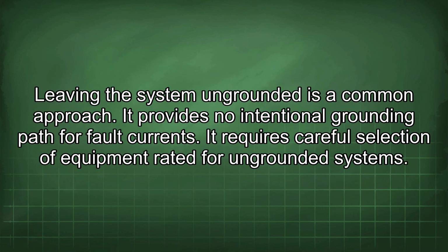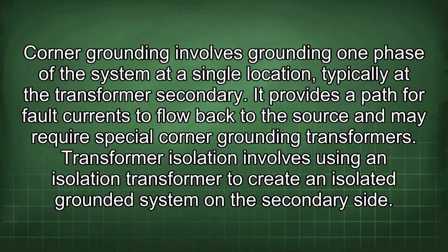Leaving the system ungrounded is a common approach. It provides no intentional grounding path for fault currents. It requires careful selection of equipment rated for ungrounded systems. Corner grounding involves grounding one phase of the system at a single location, typically at the transformer secondary. It provides a path for fault currents to flow back to the source and may require special corner grounding transformers.